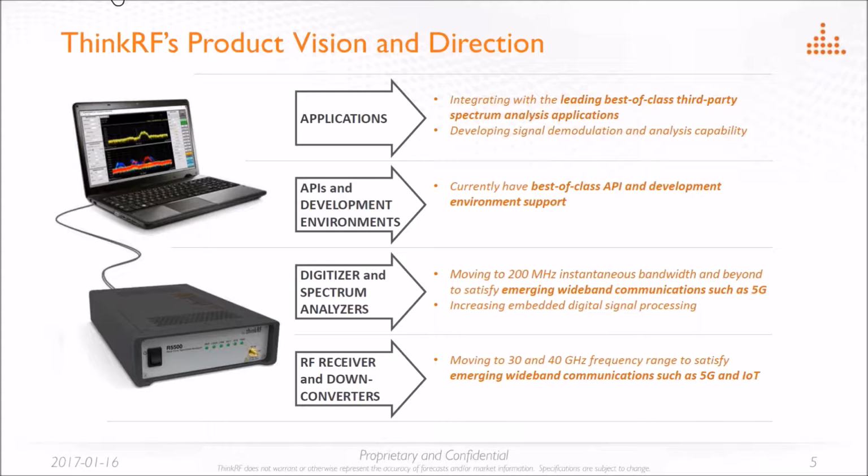I guess while we're in here, one of the questions posted was asking about real-time capture bandwidth, phase noise specifications, and typical DANL. I know it's drilling in a bit, but yeah. In terms of our DANL, our product has a DANL as good as -160 dBm per hertz.